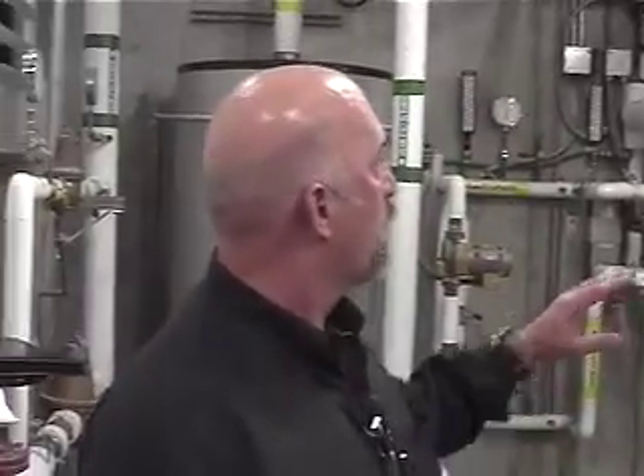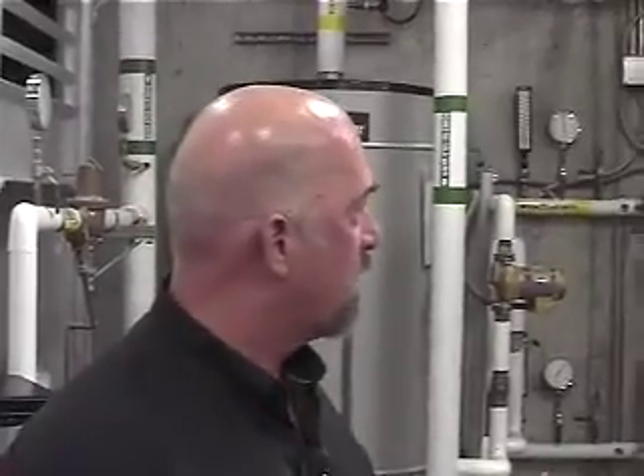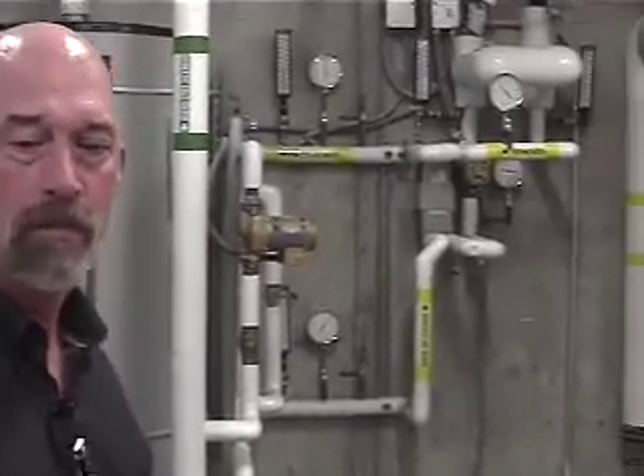Condensate pumps, steam traps, and PRVs and safety relief valves today. So, are you guys familiar with shell and tube heat exchangers? Heat exchanger, yeah. Okay. Basically what we're doing here with the PRVs is knocking down the steam pressure from what would be like 60 psi down to about 12 psi. What's your high side and your low side? High side, low side, that's what a PRV does.